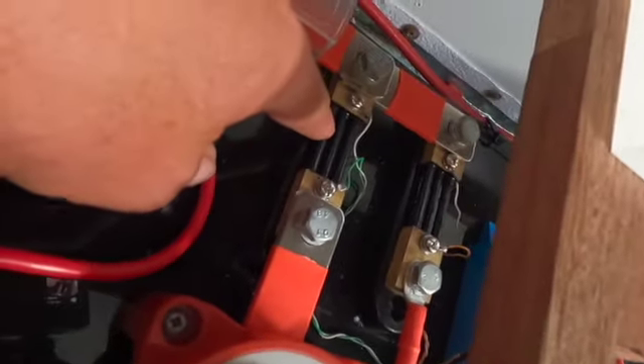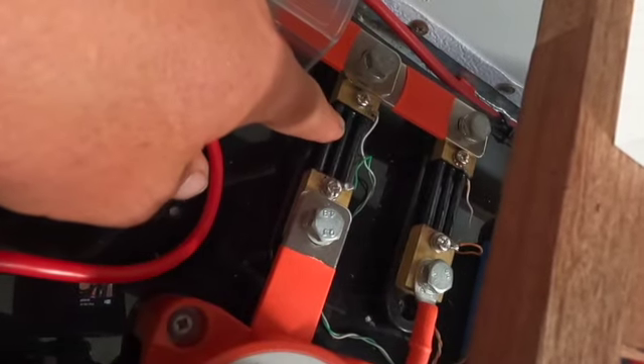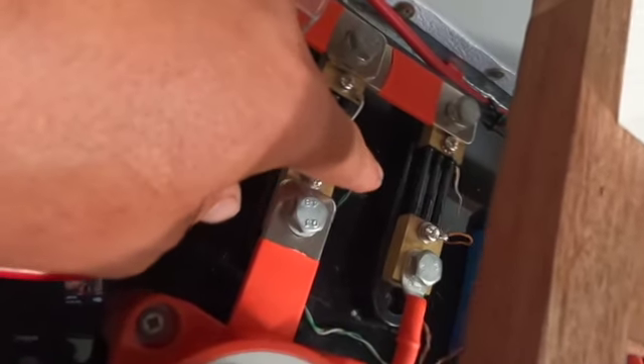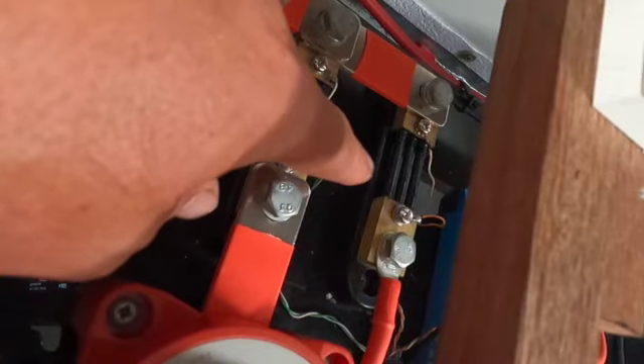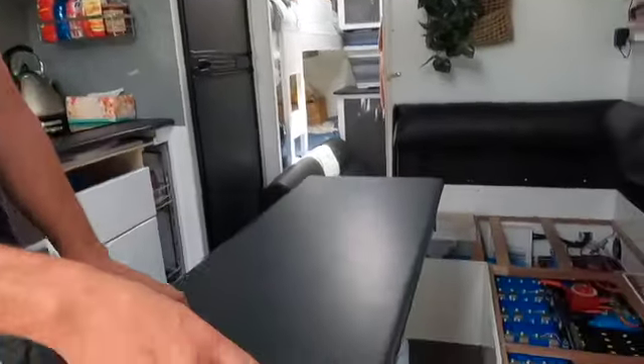So one of the shunts measures the outgoing current, and the other one measures the input current from the solar charge controllers. That allows the BMS to give us a very accurate reading of battery capacity, what's coming in and what's going out. The Electrodacus BMS down there...